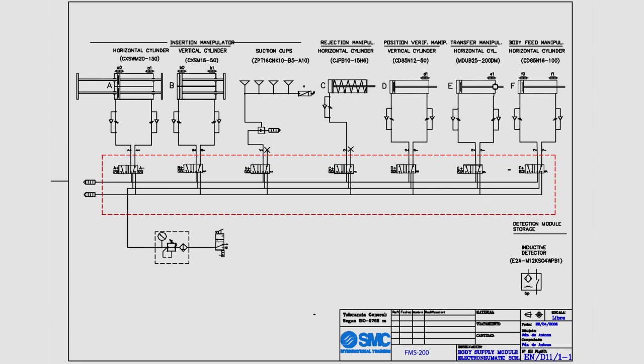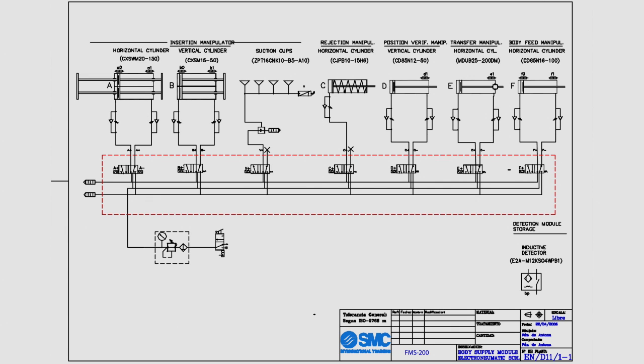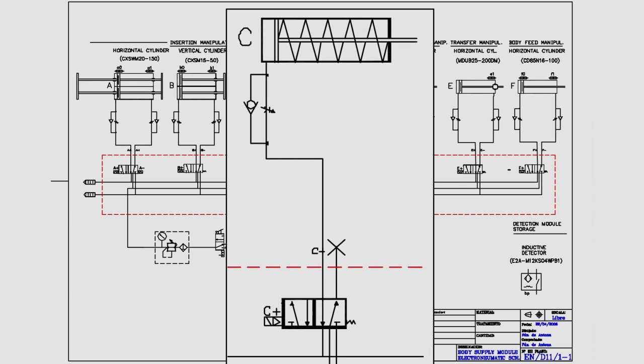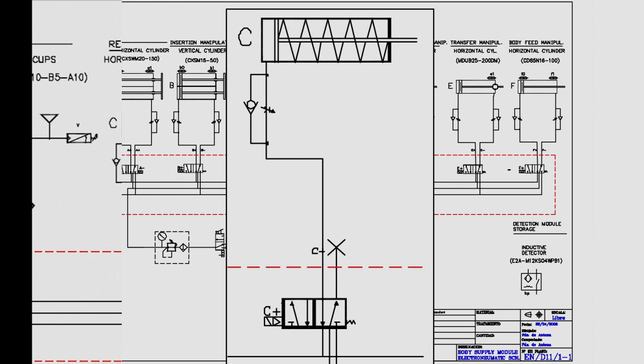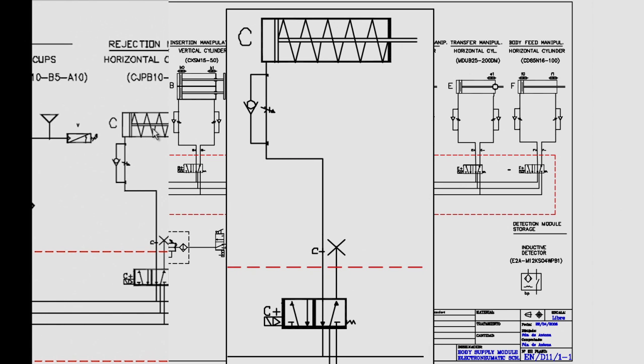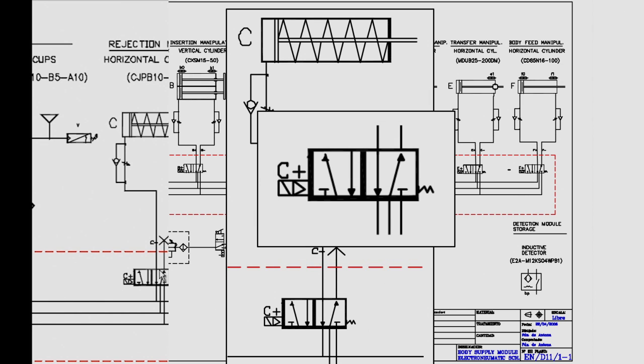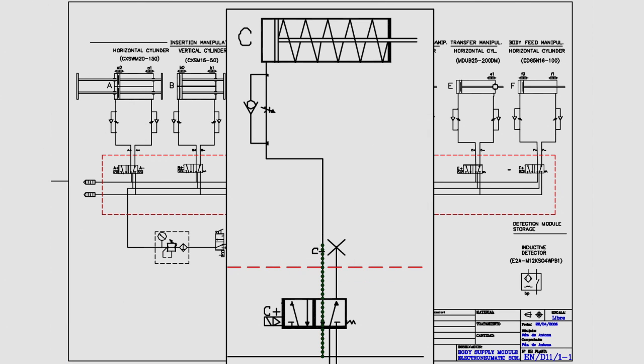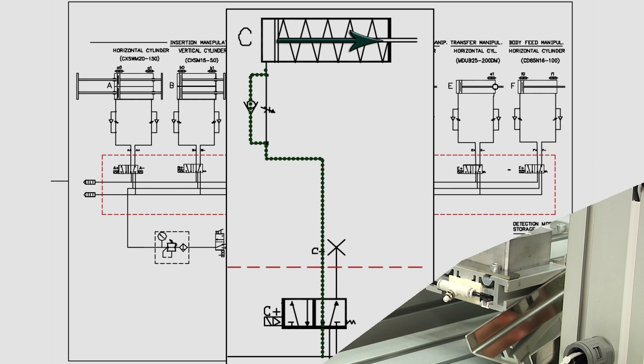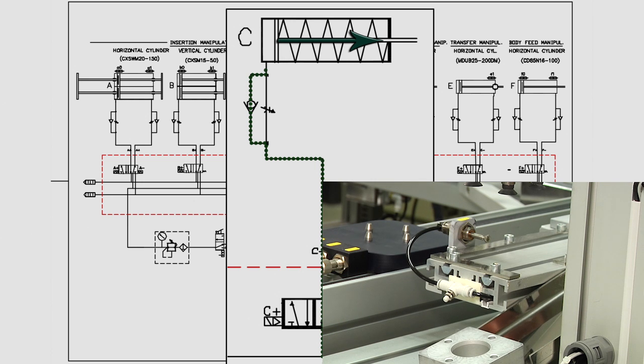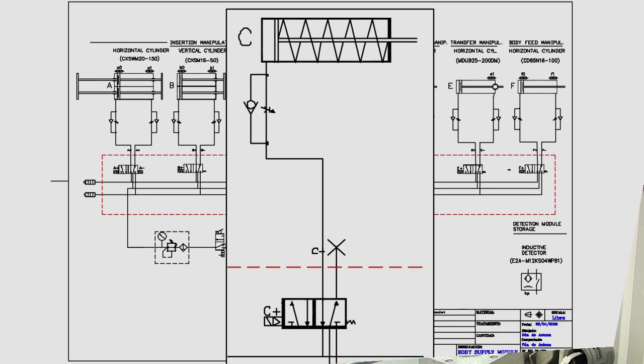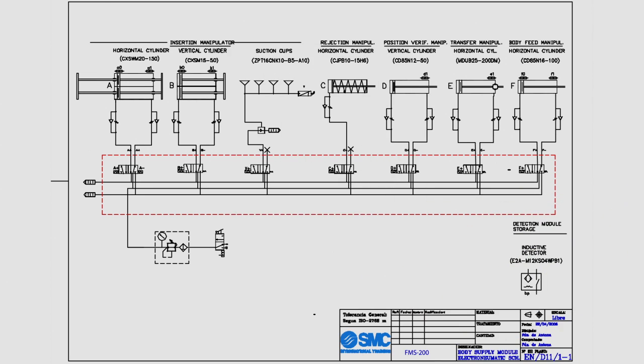On our suction cups we have a vacuum generator over here which will then trigger our vacuum switch. The rejection cylinder is a little bit different style cylinder than the other cylinders that we saw. This is known as a single acting cylinder spring return. So it has the exact same style valve that the other ones had. It's a two position valve. When we allow air to come through it's going to extend the cylinder, and as soon as we remove the air the spring is going to force it to go back the other way. So single acting cylinder, and note there is no position indicator on this cylinder.